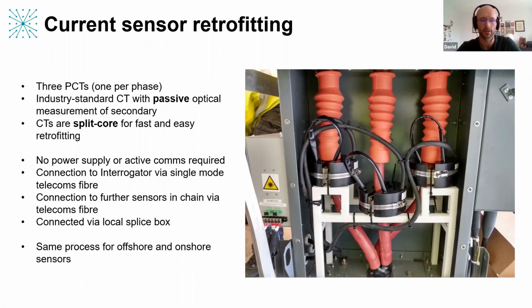The only connection that's required here is single mode telecoms fiber to the interrogator, and then a second set of fiber that leads on to the next sensor in the chain. And this connection can be easily done via local splice boxes. Obviously, the process is very much the same for onshore or offshore installations in a turbine or substation.